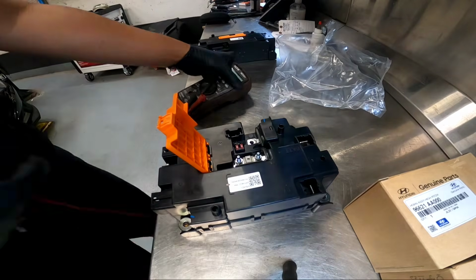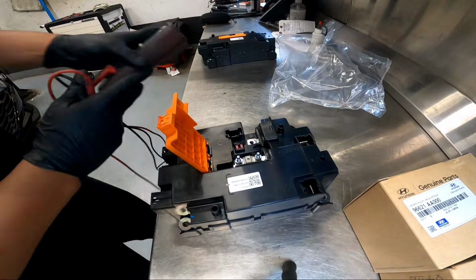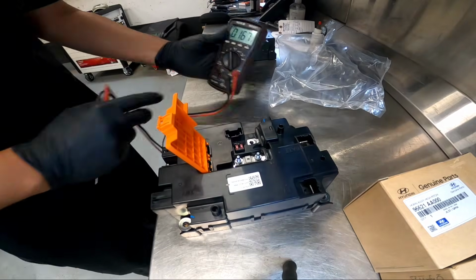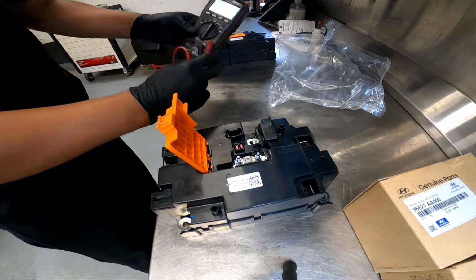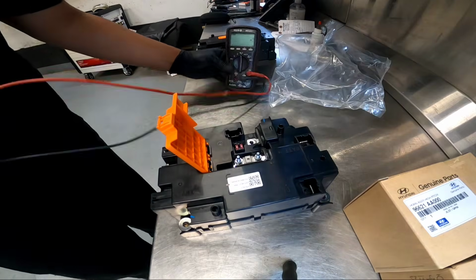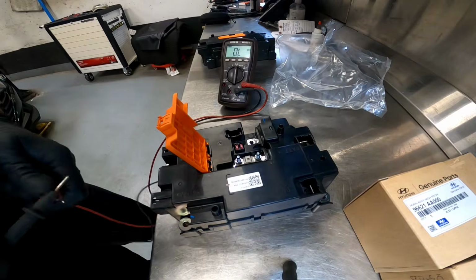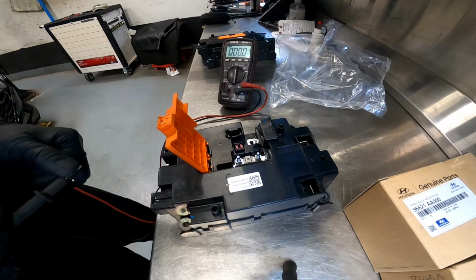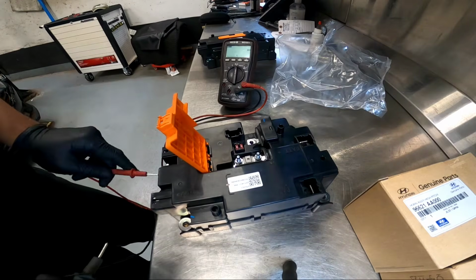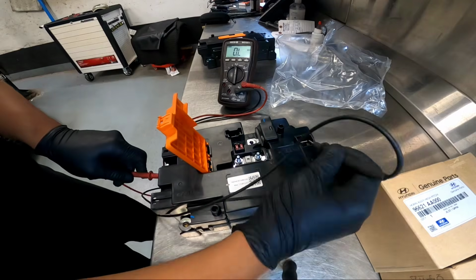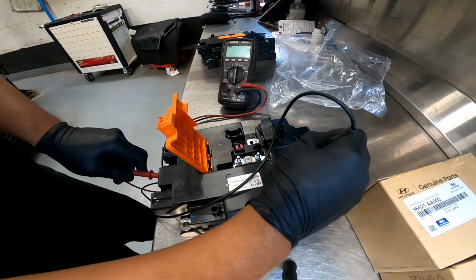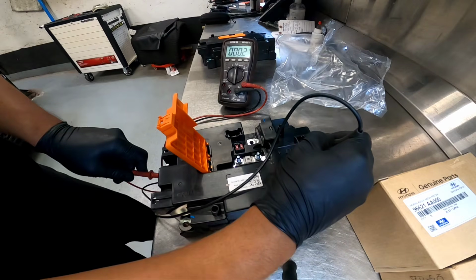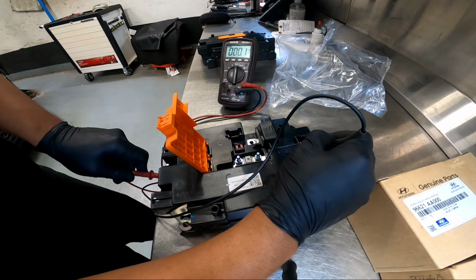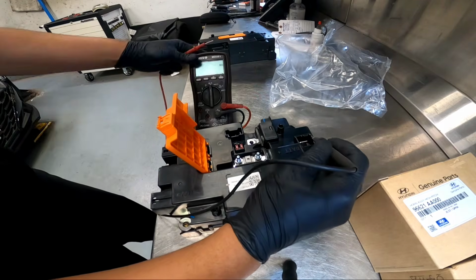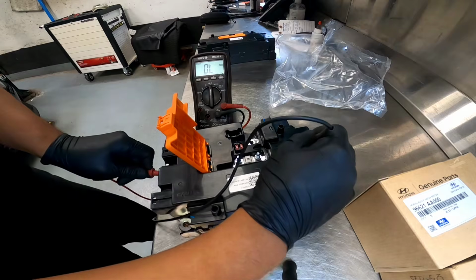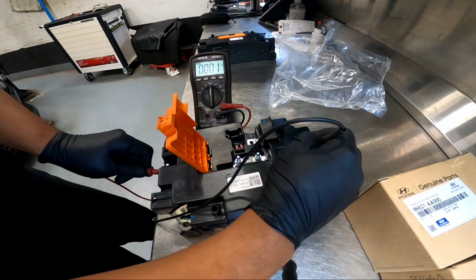Okay, so here's my meter. And go resistance. You guys can see that. Check your leads again. You got 0 ohms there. Now I'm going to go to the positive one. Positive one here. I got 0.1, as you can see there. I hope you guys can see that. And that should be open because we're not activating the relay right now. We're disconnecting the whole thing.